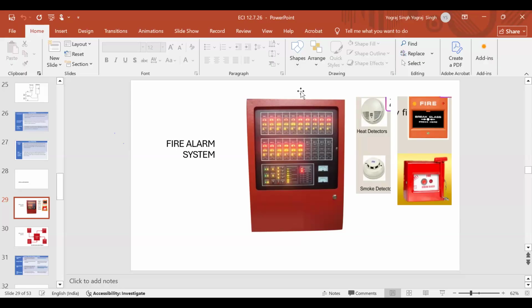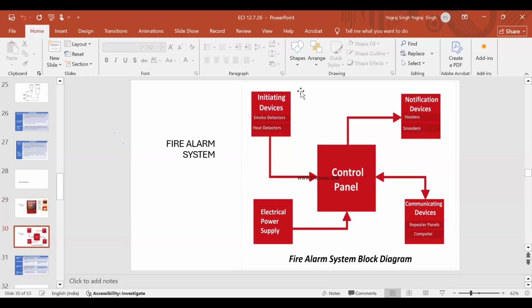So now, there is a control panel which gets power from an electric power supply. It is not your SEB supply. It is definitely your UPS or something like that. Now the control panel will receive signals from smoke detectors and heat detectors. They are provided in the building just like light points and fan points.